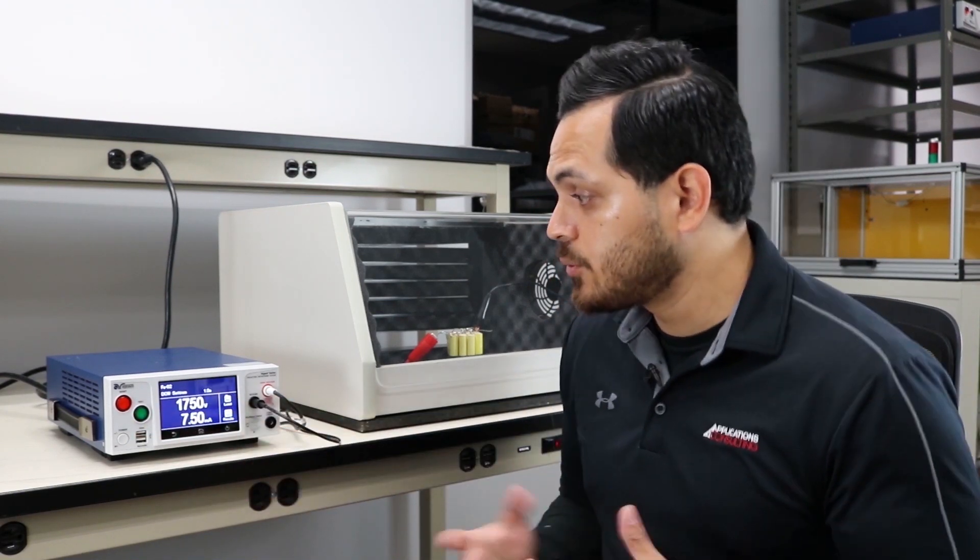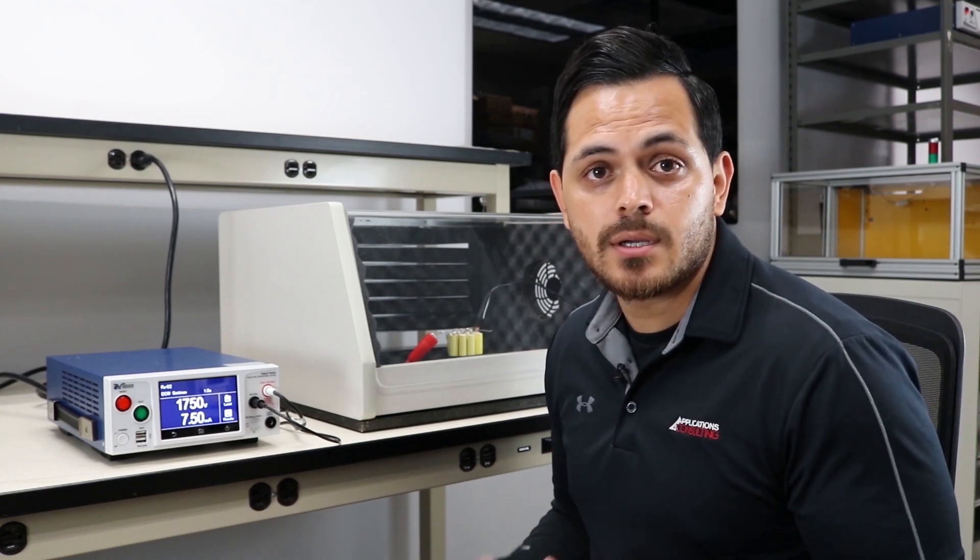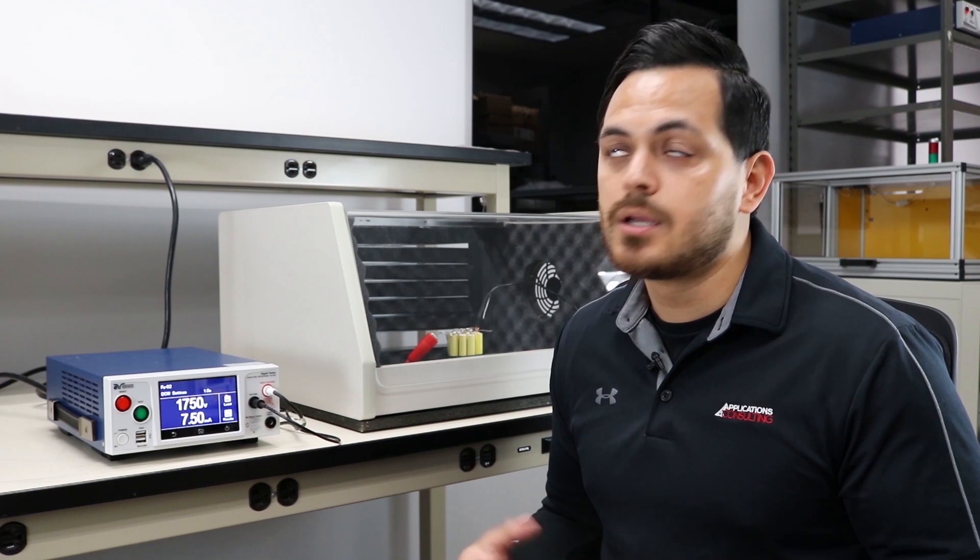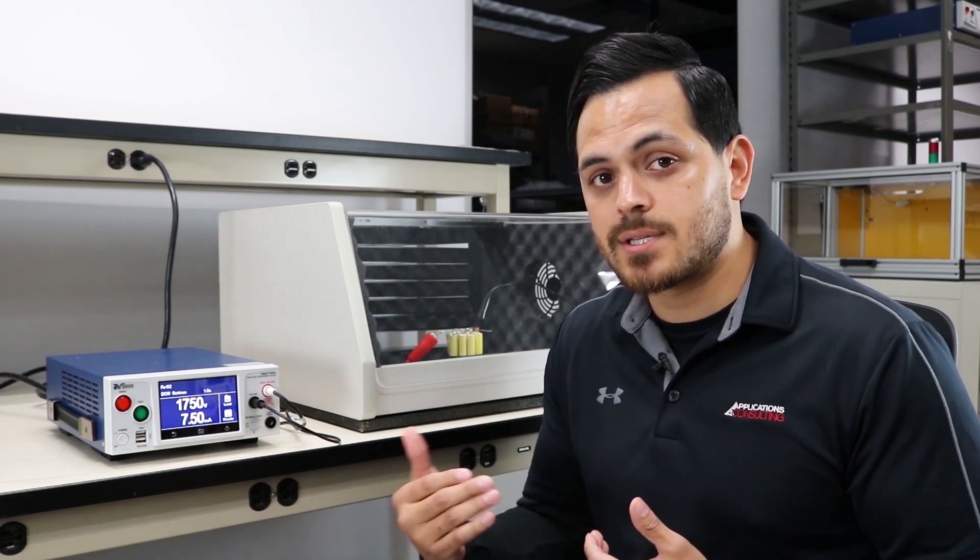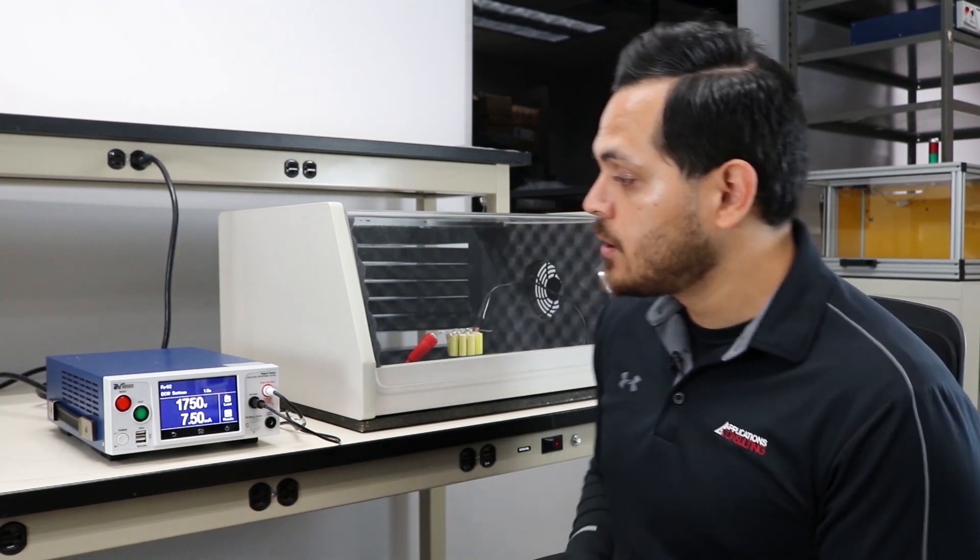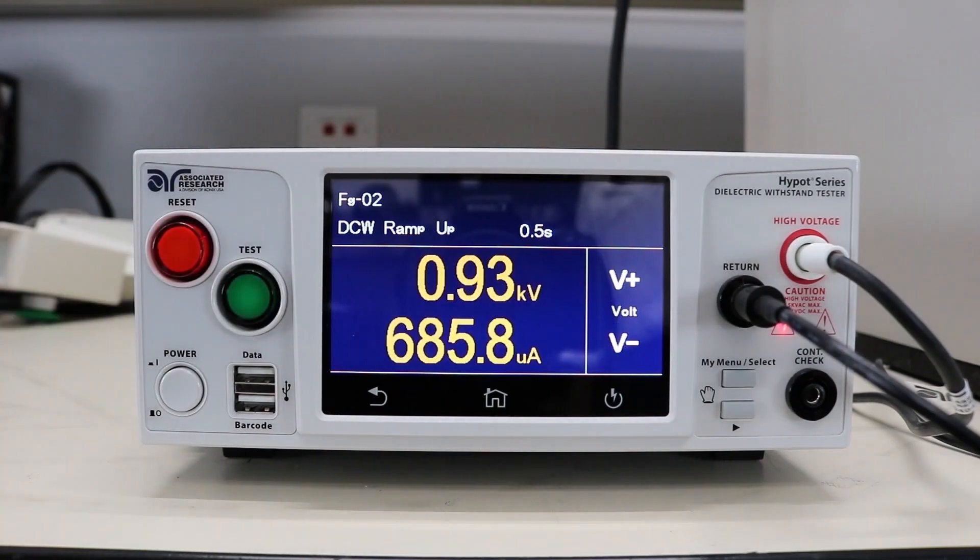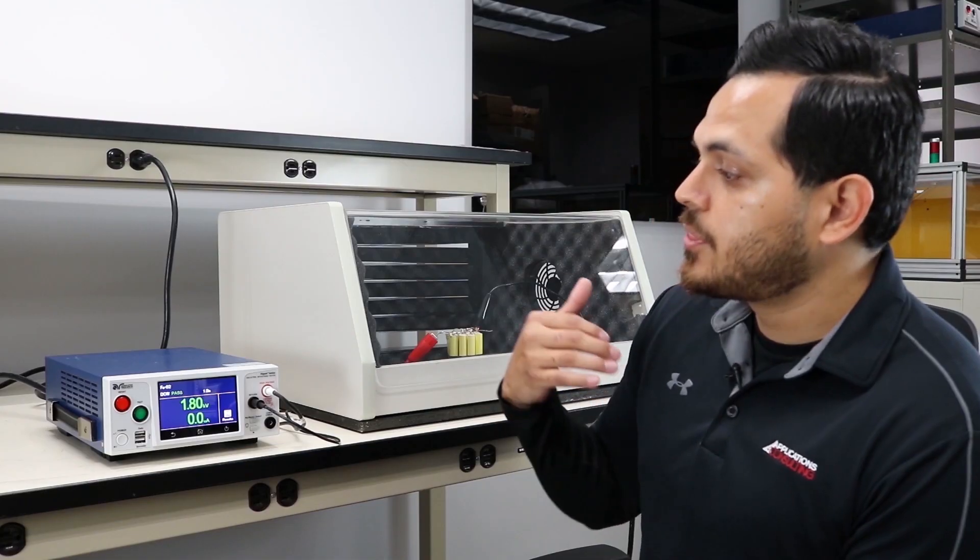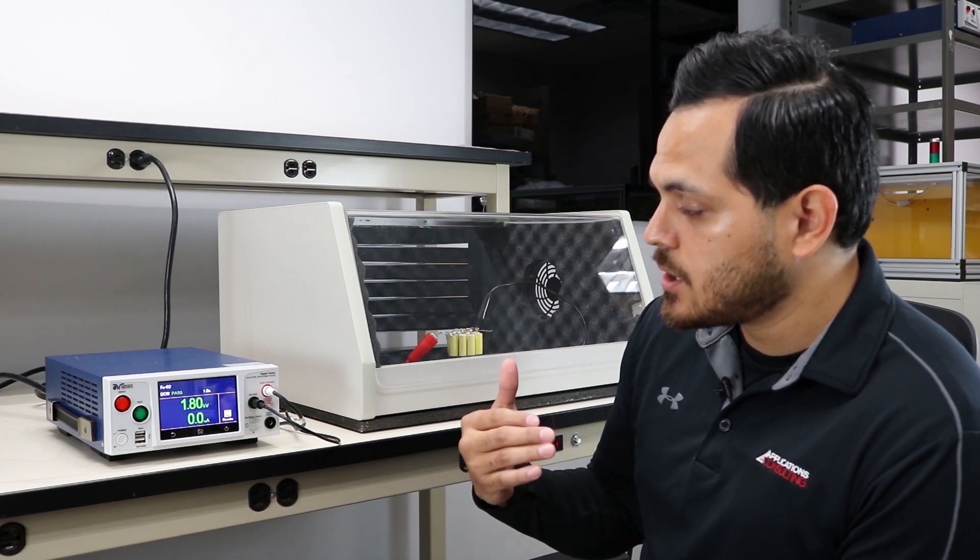So here we are, same DUT, 1750 volts which is the equivalent of the AC peak voltage of the test we just ran, which is how standards outline the necessity to make sure you're testing at an equivalent voltage. We're going to run this test.